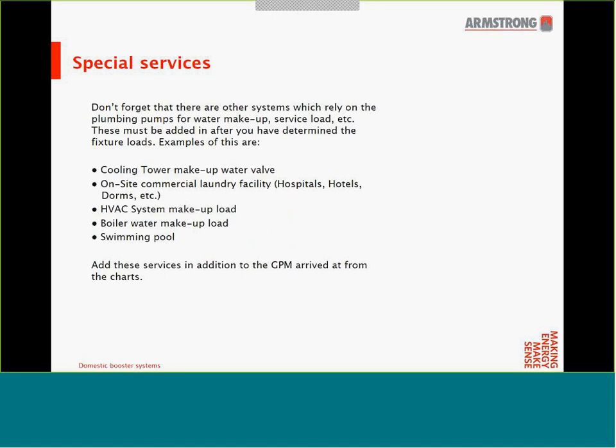Don't forget that there are other systems which rely on plumbing pumps for water makeup, service load, etc. These must be added in after you have determined the fixture load. These include cooling tower water makeup, on-site commercial laundry facilities such as for hospitals, hotels, and dorms, HVAC system makeup load, boiler water makeup load, and any water for swimming pools. These services are added in GPM in addition to the GPM arrived at from the charts.